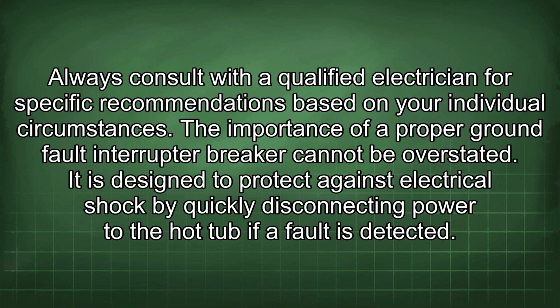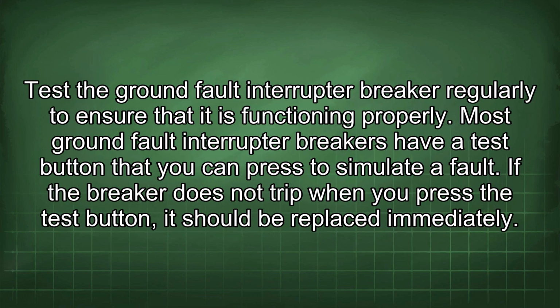The importance of a proper ground fault interrupter breaker cannot be overstated. It is designed to protect against electrical shock by quickly disconnecting power to the hot tub if a fault is detected. Test the ground fault interrupter breaker regularly to ensure that it is functioning properly. Most ground fault interrupter breakers have a test button that you can press to simulate a fault. If the breaker does not trip when you press the test button, it should be replaced immediately.